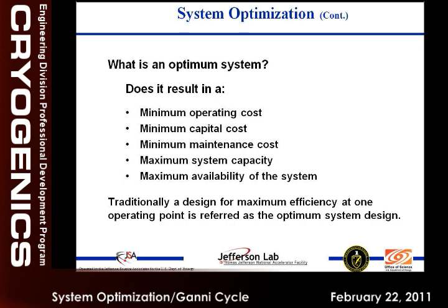And fortunately, traditionally, when I was a vendor selling these machines for a living, it always meant giving a system maximum efficiency at the maximum design point. That's all it meant. And we tried to optimize the heck out of it at that point to make sure we scored the highest in the scoring, because the labs and all these people use various scoring mechanisms, and obviously it's not just the cost they select the vendor from. So a lot of effort goes into maximizing the efficiency at one point. What I want to bring out here is that can be misleading, and it may not be to your best advantage as a user to specify it in that fashion.